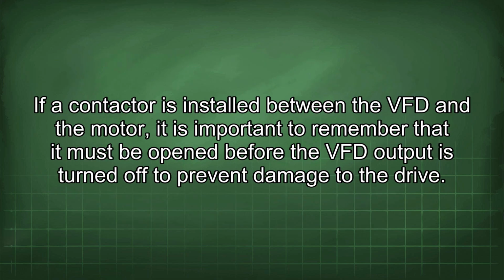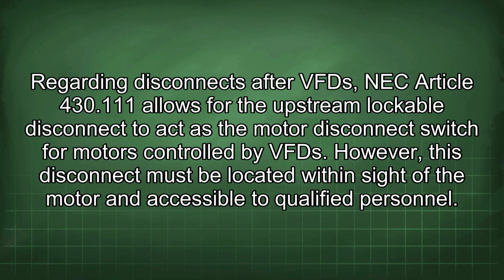If a contactor is installed between the VFD and the motor, it is important to remember that it must be opened before the VFD output is turned off to prevent damage to the drive. Regarding disconnects after VFD, NEC Article 430.111 allows for the upstream lockable disconnect to act as the motor disconnect switch for motors controlled by VFD. However, this disconnect must be located within sight of the motor and accessible to qualified personnel.